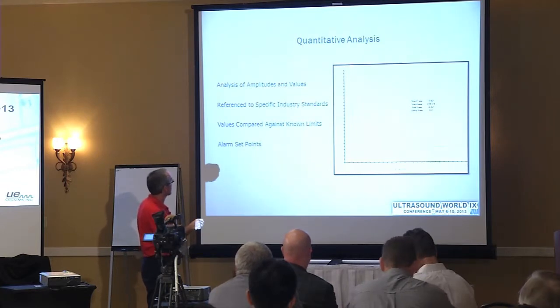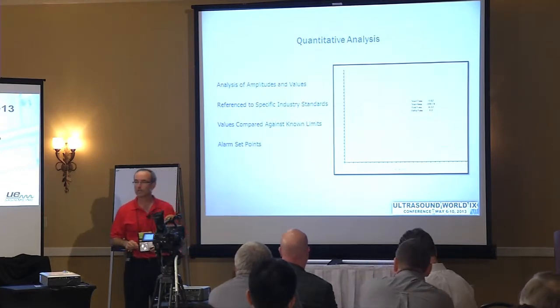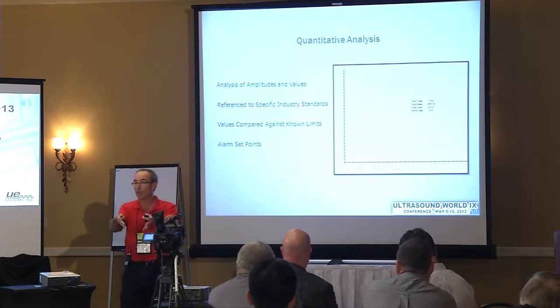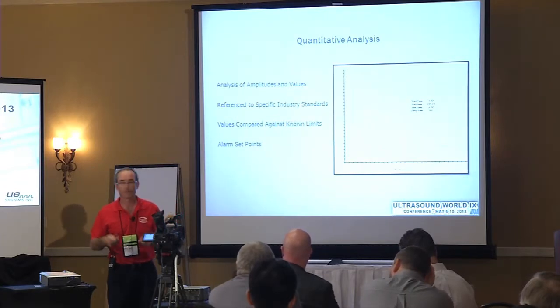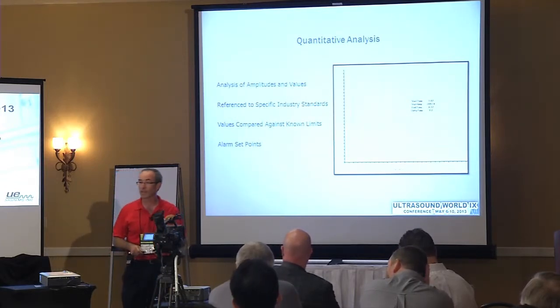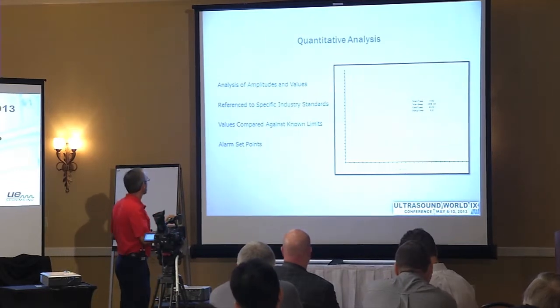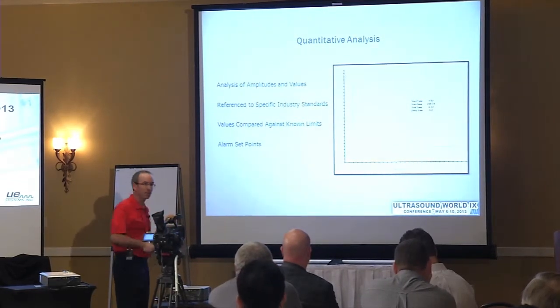So for quantitative, I want to know exactly what that value is. The motor manufacturers basically say, hey, we expect a certain amount of inrush, and if you're not getting that, it's a problem. So it's a key element — industry standards are usually supporting us on that.